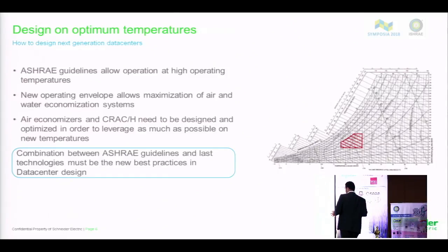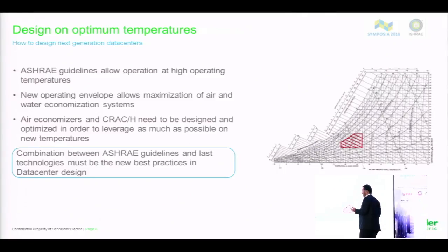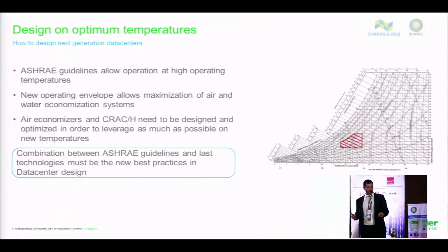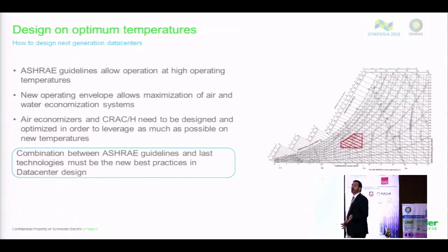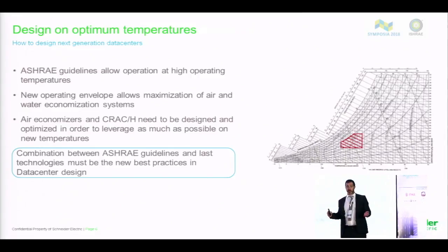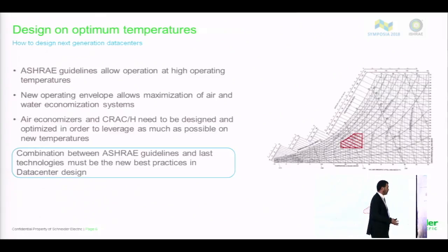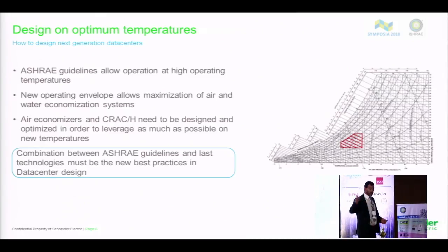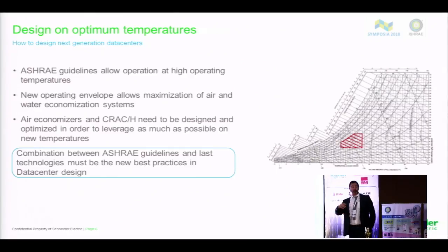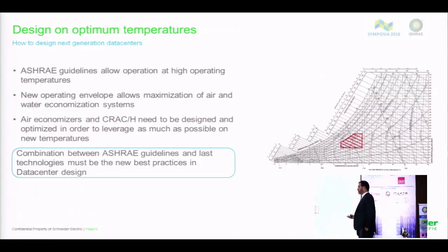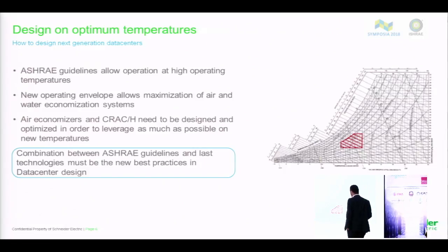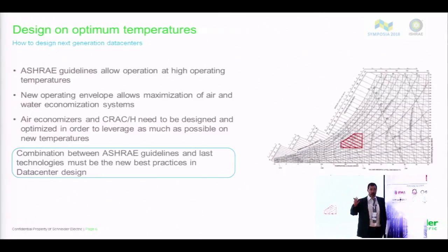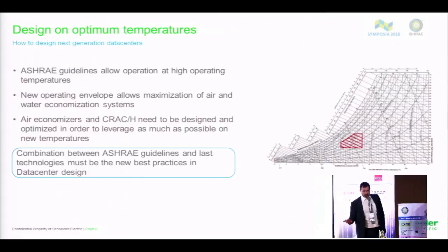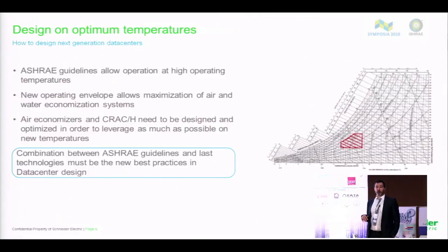If we look at the ASHRAE guidelines, ideally it is possible to increase the ambient temperature in the data center much higher than in the past, up to 27 sometimes, knowing that a 27-degree discharge in the data center may be a challenge because it is really at the edge. So for sure, 27 degrees is probably too much. Not all the colocators accept this, not all the customers accept it. However, the message is pretty clear. Let's try to design as much as possible at a high temperature. A good number is 25, 26. 24 is still good, but could be improved.